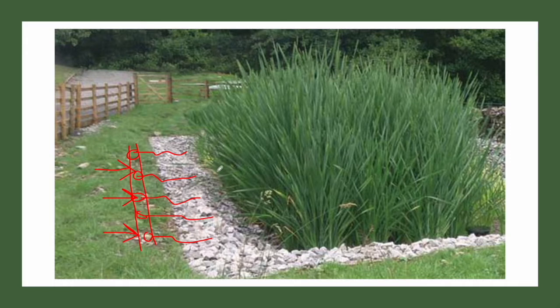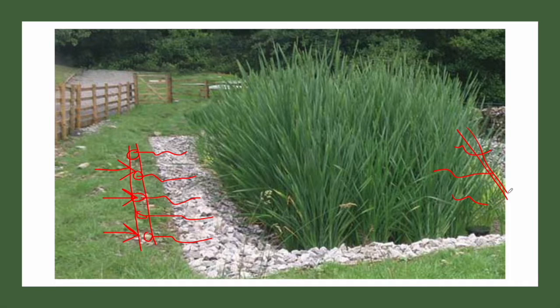The wastewater flows through the gravel media at a depth of around 40 to 50 centimeters and undergoes treatment. Then the treated wastewater exits through a perforated collection pipe and can be reused for irrigation, or further treated using a tertiary process such as chlorination or UV disinfection for safe disposal, depending on the regulations of the country.